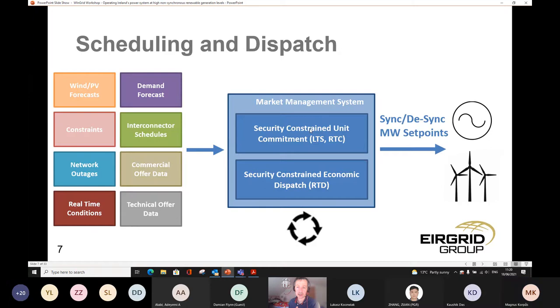This determines what set of conventional units, what units we need to have on the system. If it's high wind, we can take conventional units off. If it's low wind, we need to maybe schedule conventional units to come on. Thermal units can take, you know, up to 12 or 14 hours to actually go from a cold off state to connecting to the system and generating. So we need to look ahead up to a day to be able to make those commitment decisions.